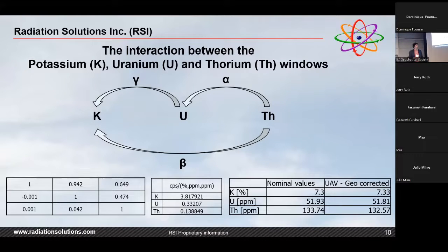That can give you already an idea of, okay, if I want to detect so many ppm at contact, so everything is done at contact here, what can I expect as a count rate? And also a good thing to do is to double check: once I get all those numbers, if I input them into my detector and redo the measurement on the pad, am I ending up with the same value as my calibration sheet says?